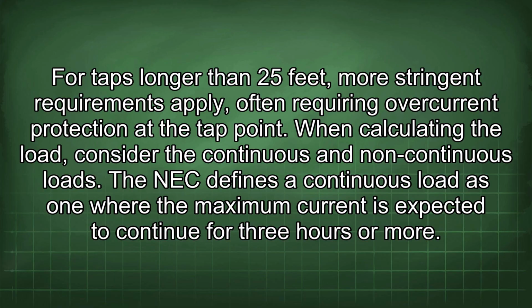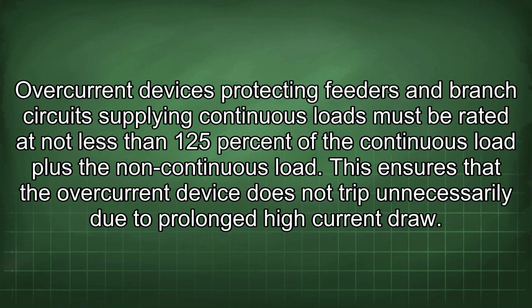When calculating the load, consider the continuous and non-continuous loads. The NEC defines a continuous load as one where the maximum current is expected to continue for 3 hours or more. Overcurrent devices protecting feeders and branch circuits supplying continuous loads must be rated at not less than 125% of the continuous load plus the non-continuous load. This ensures that the overcurrent device does not trip unnecessarily due to prolonged high current draw.